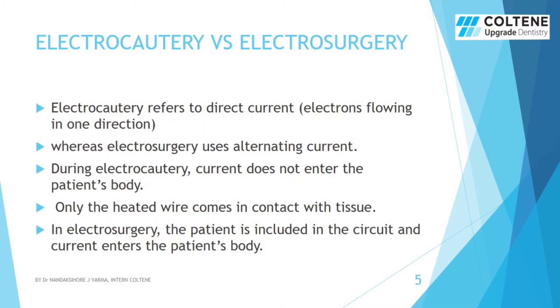Now let's see the difference between electrocautery and electrosurgery. In electrocautery, DC current is used, while AC is used in electrosurgery. During electrocautery, current does not enter the patient's body, while it does in electrosurgery.